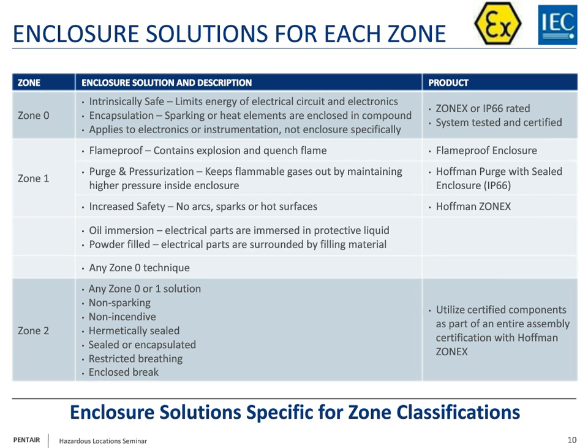Zone 1, you have 3 different options. Core options is what I'll call them for control panels. You have flameproof, which is similar to explosion-proof. The idea here is it contains the explosion, quenches a flame as those explosions exit the enclosure. We'll talk more about that as we move forward.